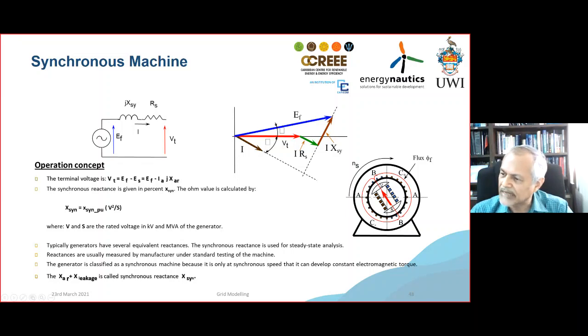And this is your rotor, which is actually providing the field for my system to generate my power. And the rotor is what is being driven by the turbine or the motor or the generator that the machine that you have is turning. And actually this turbine with the machine that you have is turning would be what we will call, and you'll see it in the future, part of what is called the inertia of your system, of this particular synchronous generator.